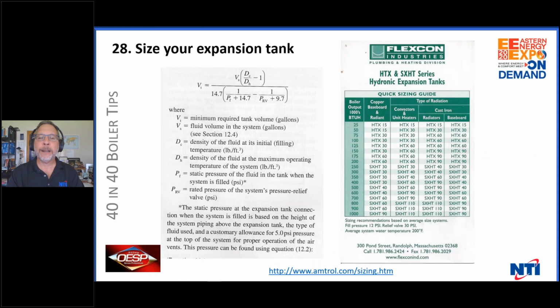Size your expansion tank correctly. I still use today, still at my desk, the chart that I copied to put this slide up. It's quick and simple. It's easy. A number 15 Amtrol or a number 30 Amtrol tank doesn't fit all installations. You have to take into consideration the volume, which is why that formula is there.